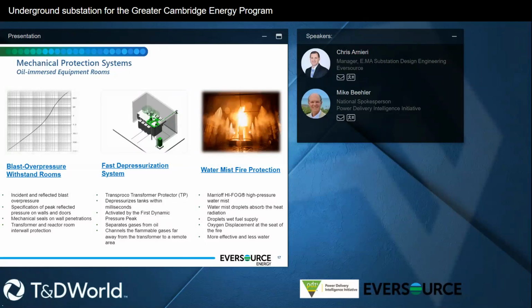So that's when we looked out to do a fast depressurizing system on the transformer. We partnered with TransProCo for a transformer protector that they offer. That system depressurizes the tank within milliseconds. It's essentially activated by the first dynamic pressure peak. And then the way it actually operates is it separates the gases from the oils of the transformer. And then it channels the flammable gases. And in this case, we actually channel it all the way back up to the topmost point of the exhaust shaft that we'll talk about in a little bit.